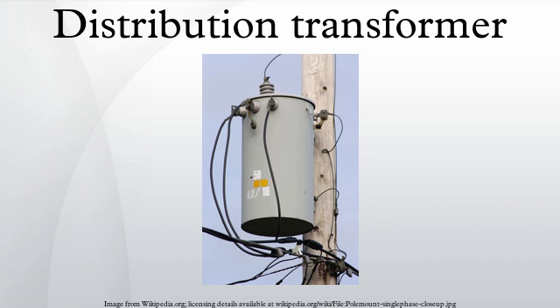Higher secondary voltages, such as 480 volts, are sometimes required for commercial and industrial uses. Some industrial customers require three-phase power at secondary voltages. To provide this, three-phase transformers can be used. In the U.S., which uses mostly single-phase transformers, three identical single-phase transformers are often wired in a transformer bank in either a Y or Delta connection to create a three-phase transformer.